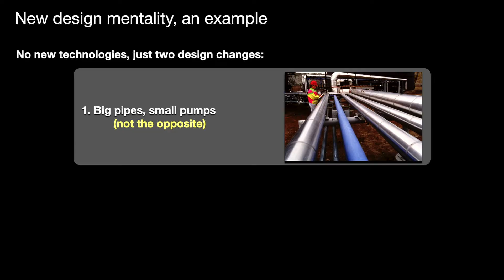But by then, A and B are far apart. Other stuff got in between them. They're at the wrong height. They face the wrong direction. And by the time the pipe snakes its way across the space, all dressed in neat right angles like they teach us in trade school, it has about 3 to 6 times the friction it would have had with a straight shot.